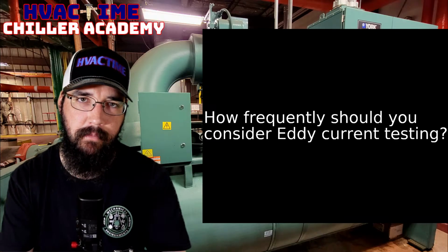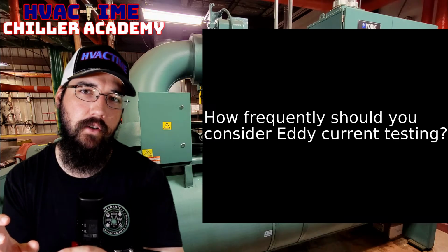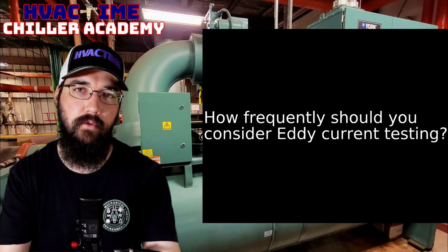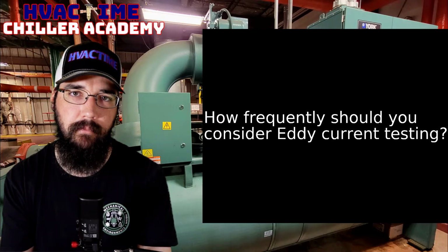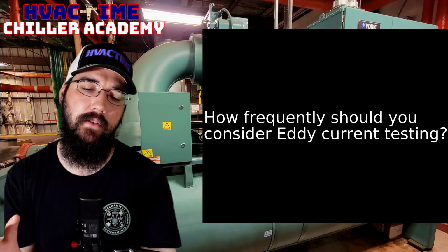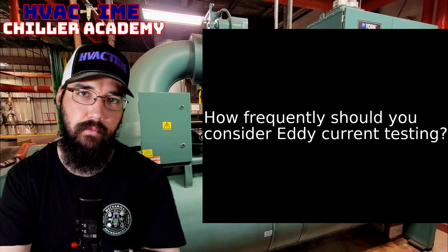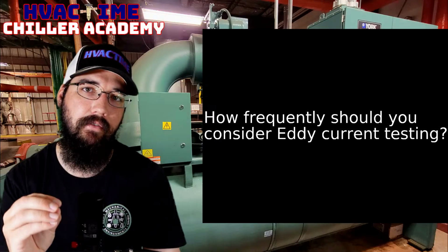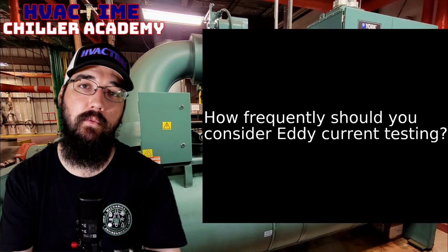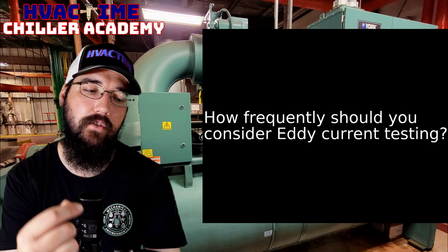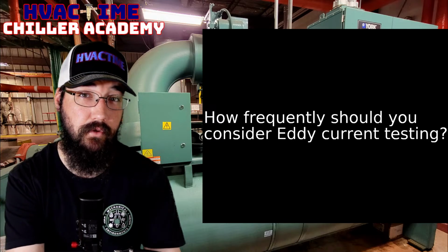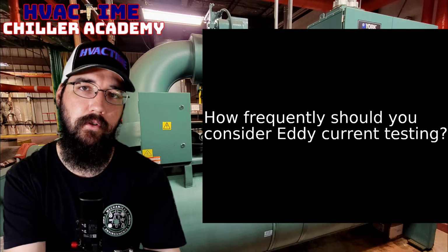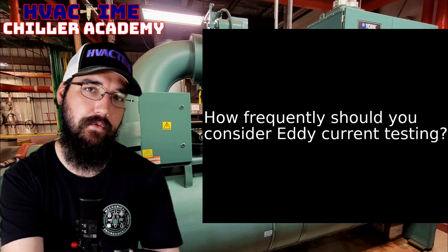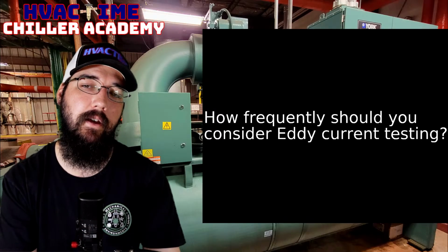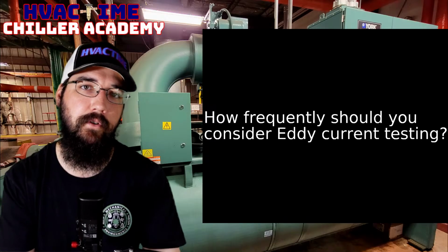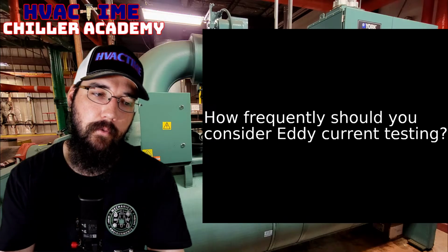An eddy current test uses a probe, and you want to do this after you brush the tube. You'll drain the barrels down, open the end bells or water boxes, and brush those tubes out to make sure everything's clean. You want as accurate a test as possible, so you don't want anything in the way. It's also good to know if you have an obstruction in a pipe before you send the probe down, so you can figure out ahead of time which tube to be careful with.